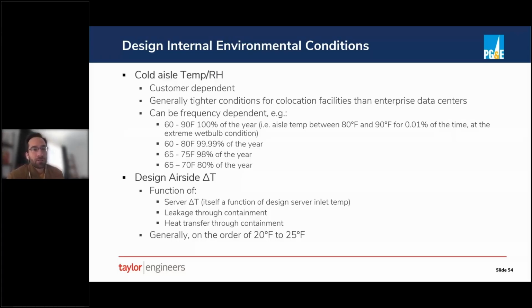One interesting thing that you'll find is that in contrast to there being just a fixed environmental condition within the cold aisle, owners might have a frequency dependent requirement. They might say, for instance, that, look, we need it to be between 60 and 90 degrees Fahrenheit 100% of the year, but we will allow those requirements to be relaxed during extreme conditions. So during, say, really, really hot days, it's okay if, for that 0.01% of the year, it does get up to 90, but for the rest of the year, we need it to be below 80, right? So they're becoming more strict for, I guess, smaller periods of time.